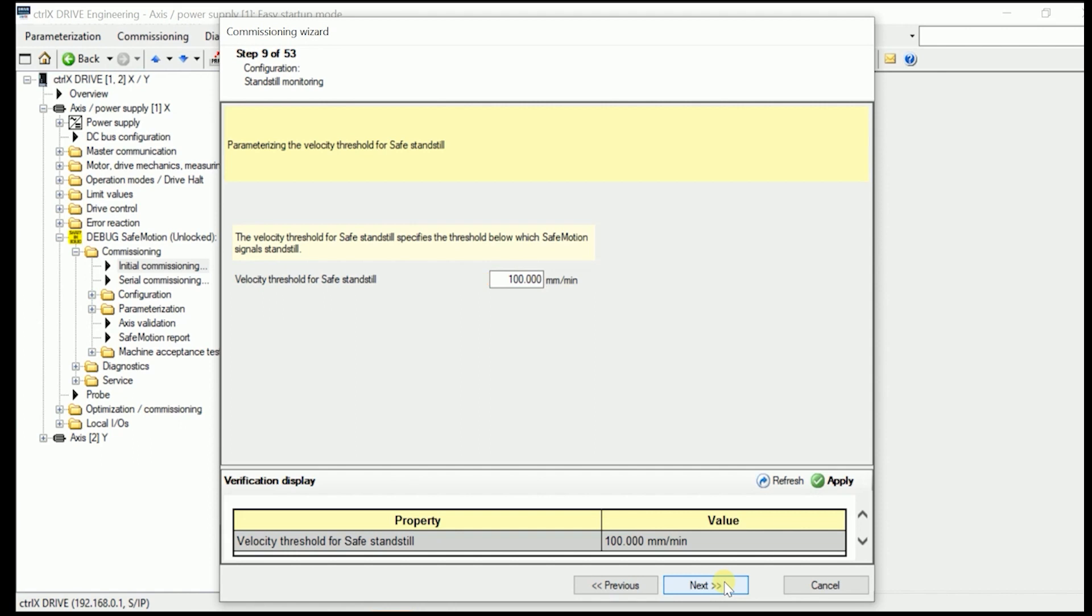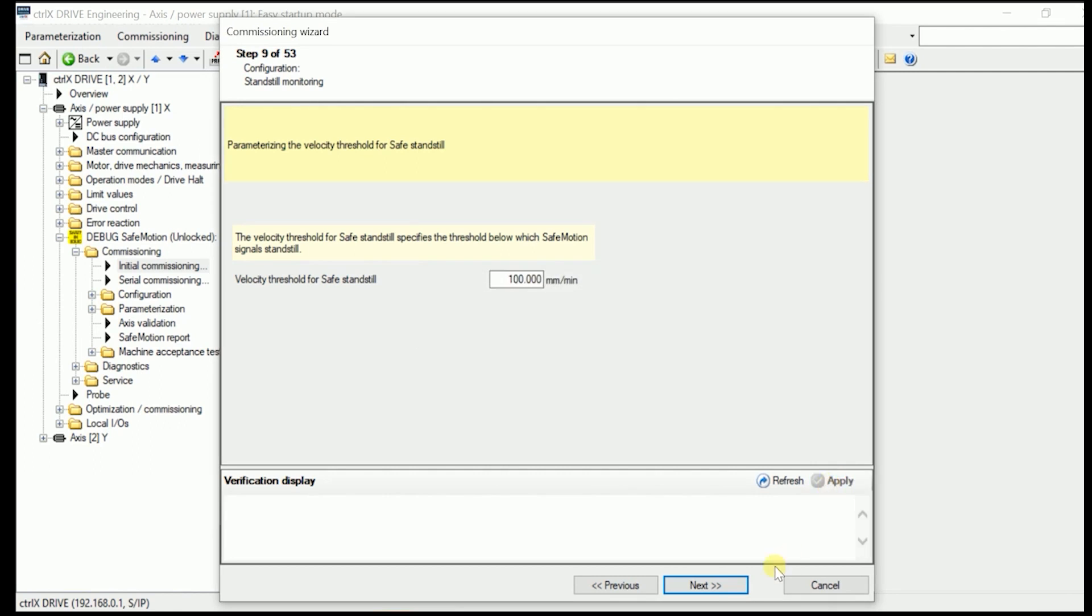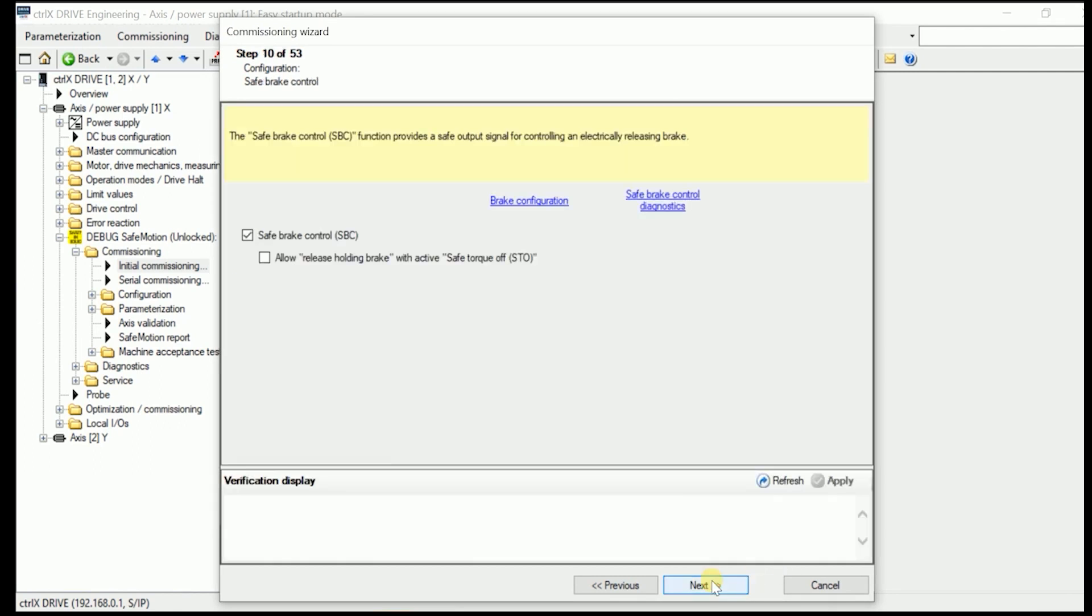And go on with the next figure we have to establish. And in here we have to tell what the velocity threshold for the safe stand still is. Like say in here it is set to 100 mm per minute. Which is a quite good figure. And we keep it in here. With pressing next.